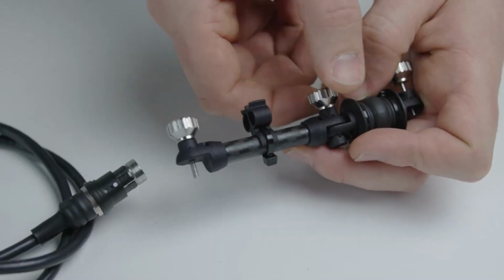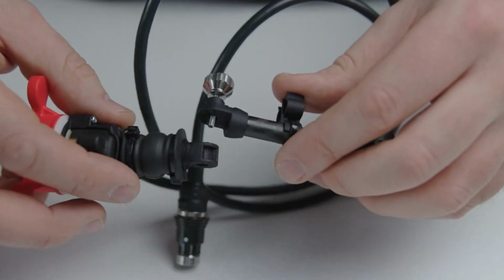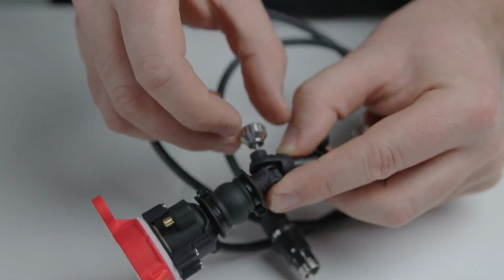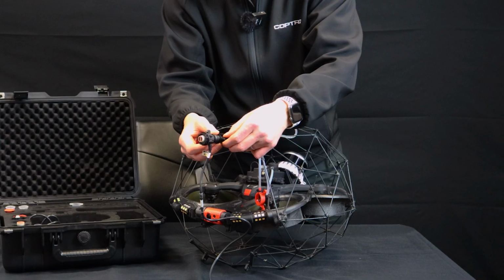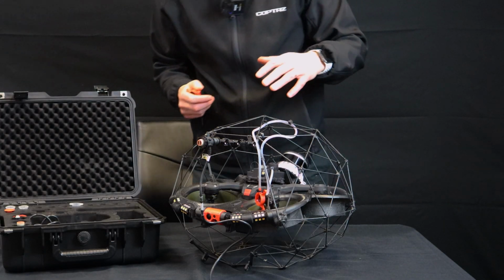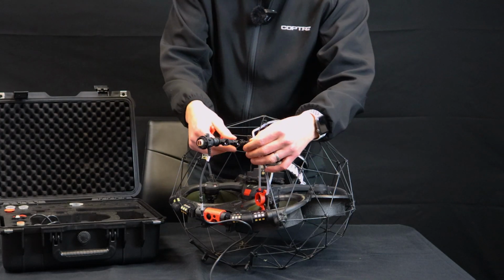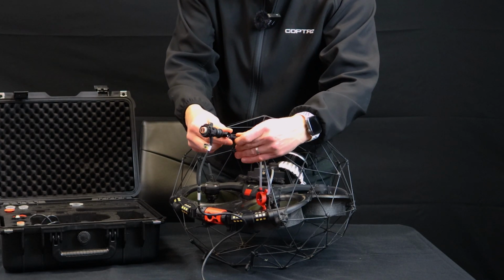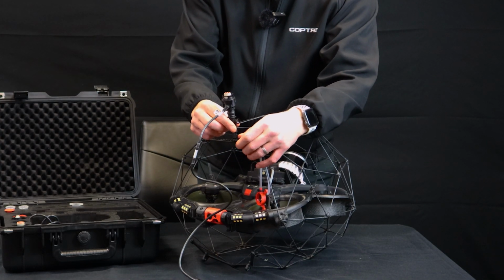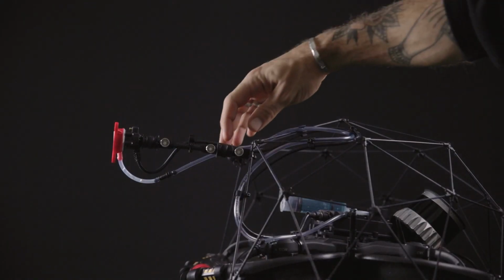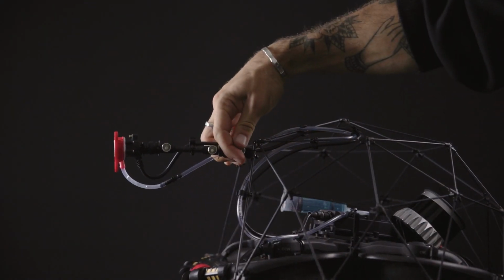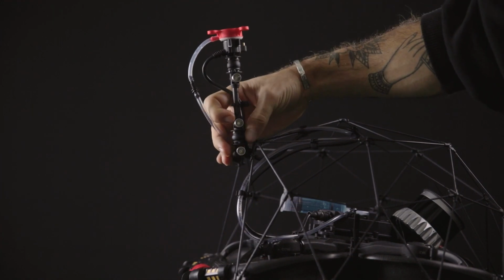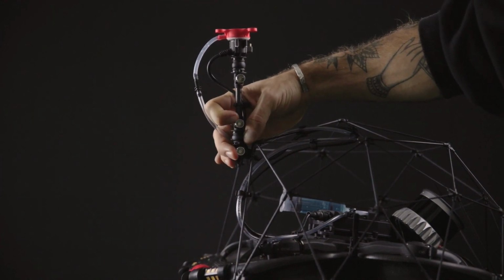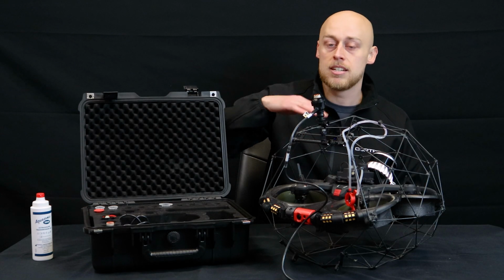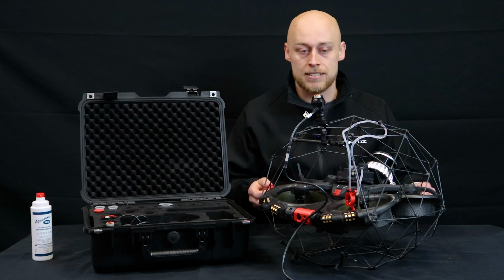The great thing about the probe arm, the long black attachment, is it can be done at different orientations. You can have it on top facing upwards, or even on the bottom. If we put it to the top, this allows for inspections or points to be captured on the top surface. So if you go into an asset, say a tank, and want the top side, you can capture that very easily.